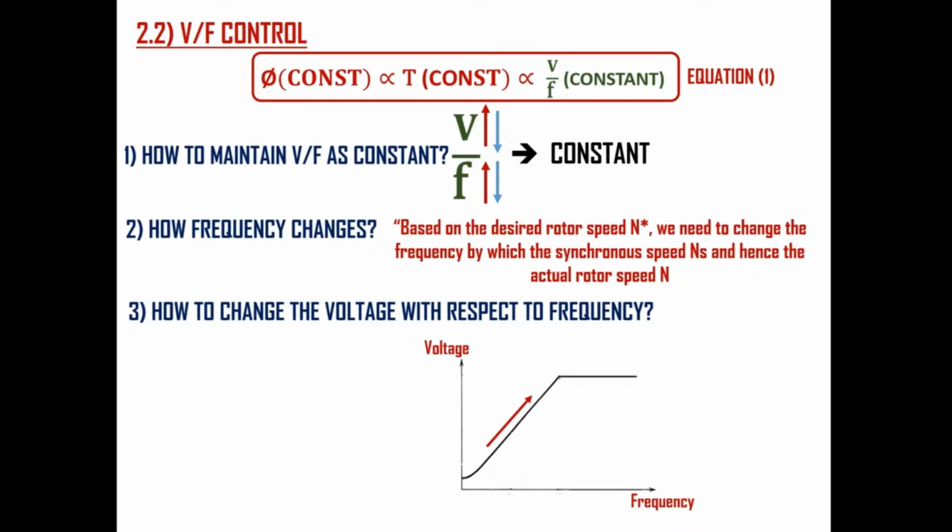The first important point is there is a need of small voltage boosting to be applied in low frequencies so that E will be approximately equal to V. It can be interpreted in another way, that it is to compensate the voltage drop in stator winding resistance R1.